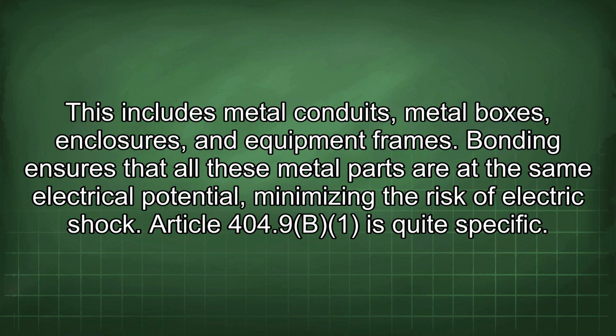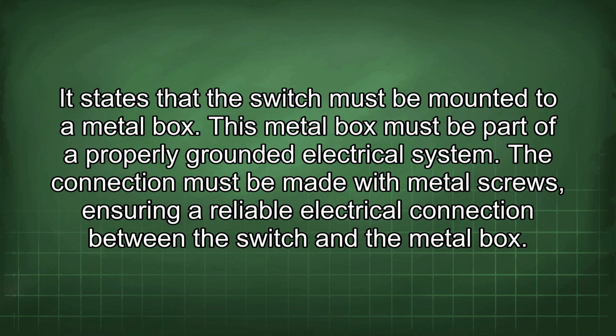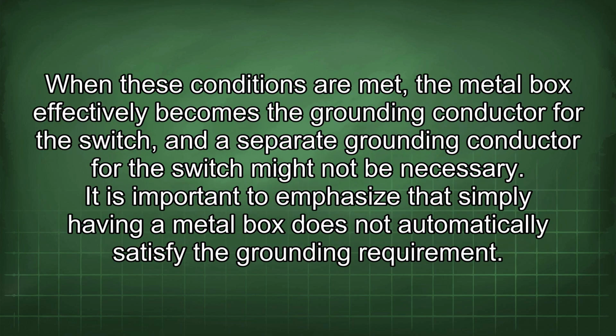Article 404.9 is quite specific. It states that the switch must be mounted to a metal box. This metal box must be part of a properly grounded electrical system. The connection must be made with metal screws, ensuring a reliable electrical connection between the switch and the metal box. When these conditions are met, the metal box effectively becomes the grounding conductor for the switch, and a separate grounding conductor for the switch might not be necessary.